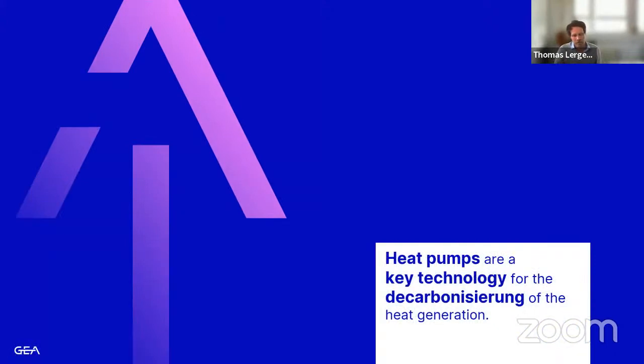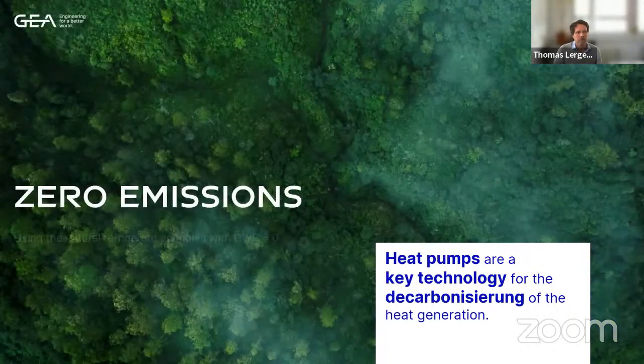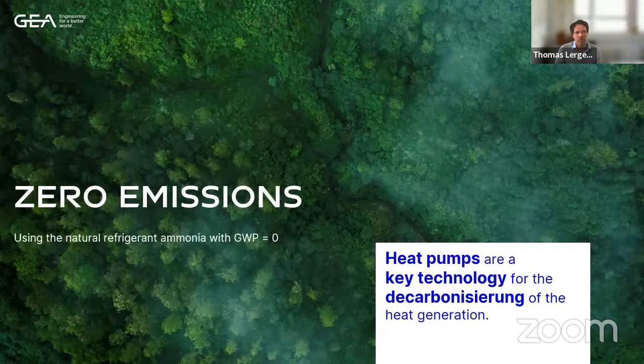In the process we saw, I was mentioning a refrigerant that evaporates and sucks up the heat, and then it liquefies and rejects the heat. That's the key functioning of any refrigeration and also the heat pump cycle. And speaking of refrigerants, we at GEA have a long history with ammonia from the cooling and refrigeration segments. And we are also using ammonia with our standard heat pumps. Ammonia is a natural refrigerant that creates zero emissions. So the so-called GWP, the global warming potential, is zero. It is also a very available refrigerant.